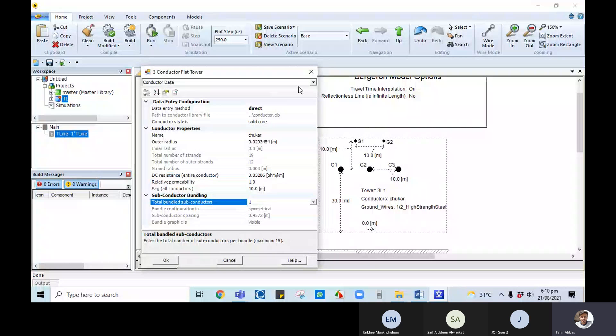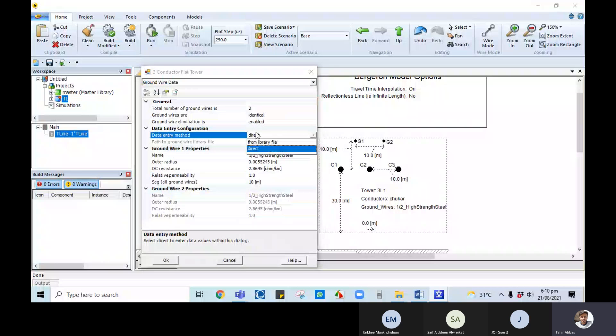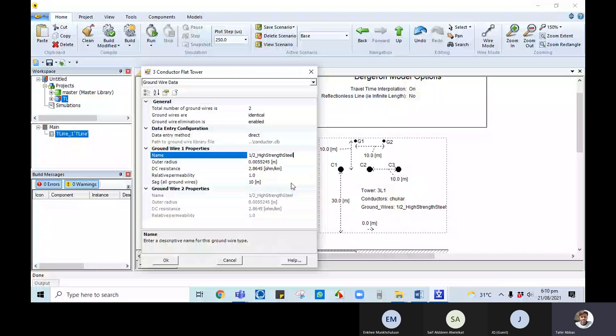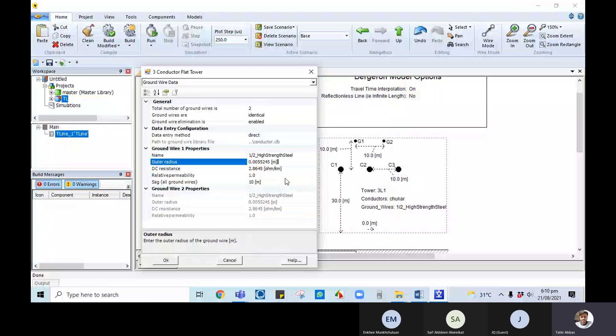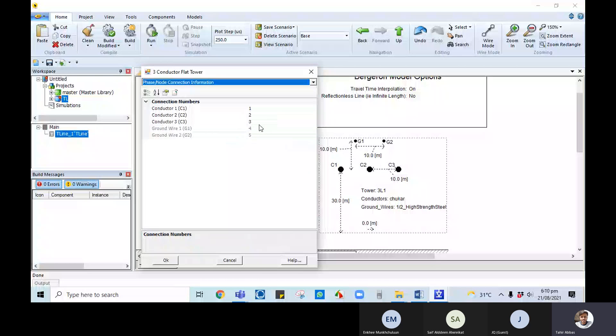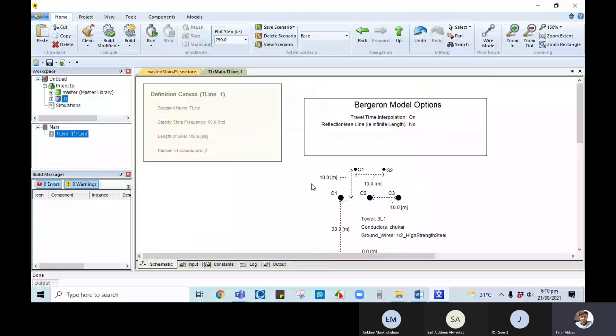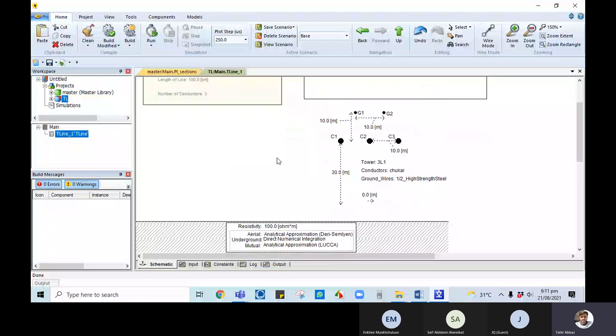Based on the conductor bundling data, there will be a difference in the parameters. For ground wire data, again we can use Direct entry mode and provide outer radius, DC resistance, relative permeability, and sag. Parameters shown in gray are calculated by PSCAD and cannot be edited — only the black-colored fields can be edited. The asymmetrical bundling position is based on transposition. Ground wires, also called shield wires, are used for the three-phase conductors.